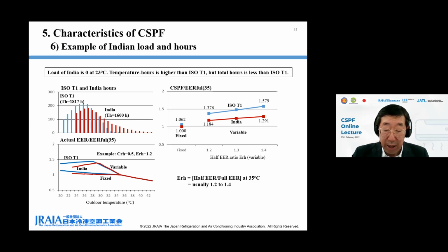The lower left figure shows actual EER divided by 35 degrees C full EER for fixed capacity and variable capacity unit. Half capacity ratio CRH and half EER ratio ERH of the example variable capacity unit are 0.5 and 1.2. When load zero temperature changed to 23 degrees C from 20 degrees C, actual EER becomes lower in the on-off zone for both fixed capacity and variable capacity unit. In addition, for variable capacity unit, the temperature of load and half capacity becomes higher and on-off operation starts at a higher outdoor temperature.